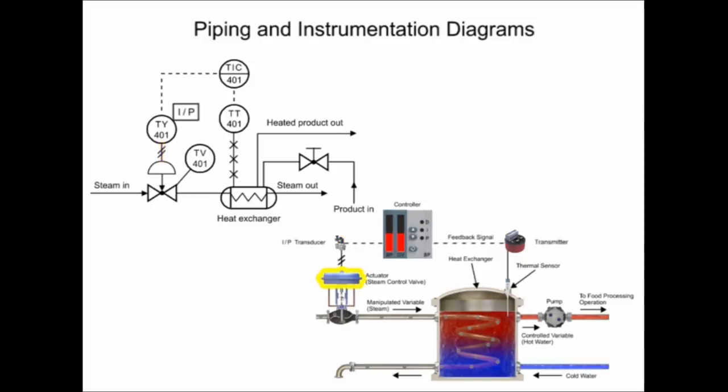The pneumatic control diaphragm actuator that opens and closes the globe valve regulates steam in the process. The actuator is represented by the half circle in the P and ID. The arrow pointing downwards from the actuator indicates a fail closed valve type.